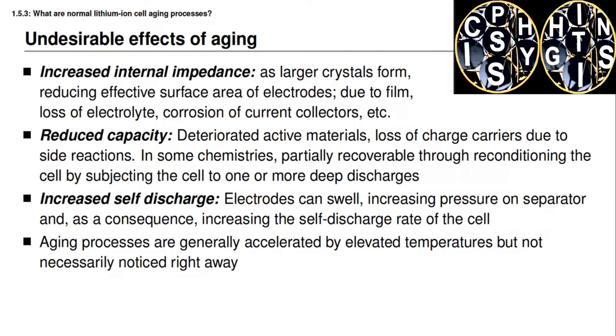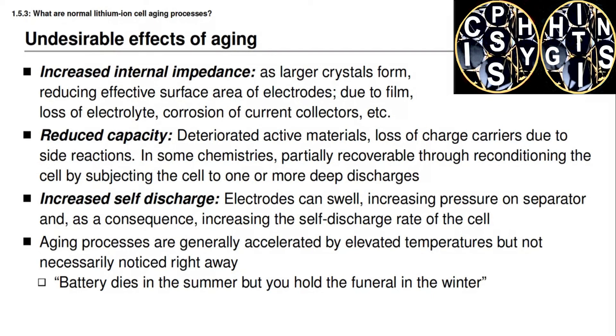Any one of the aging processes is usually accelerated by higher temperatures, and the resulting aging is not necessarily noticed right away. There's a rule of thumb that says batteries die in the summer but you hold the funeral in the winter. The aging mechanism was probably accelerated by hot summer temperatures, but hot temperatures also result in lower cell resistance. Cell resistances are lower at warm temperatures and higher at cold temperatures, so even though effective resistance is increasing due to aging, you don't notice it until winter, when cold temperatures cause the overall resistance to rise and you realize the cell has actually failed.